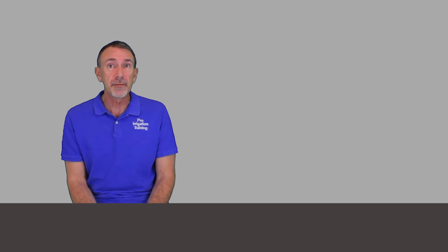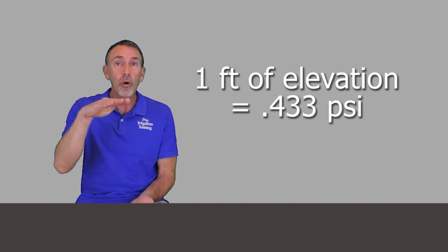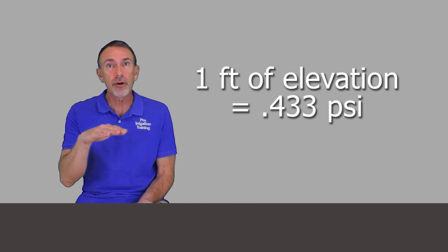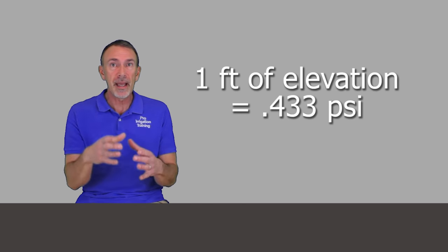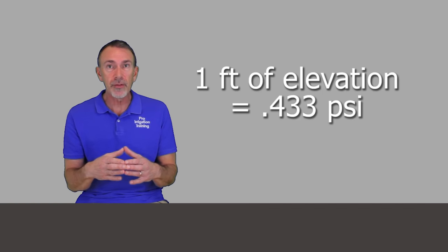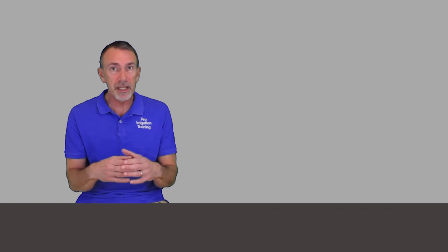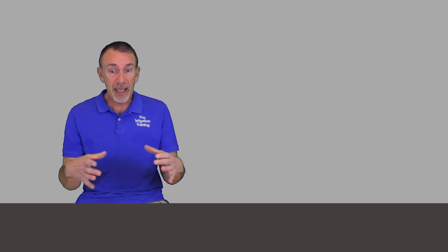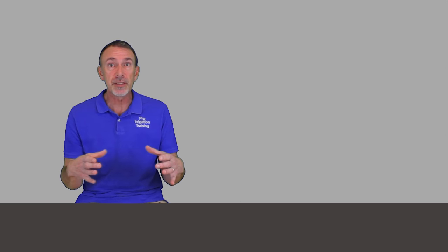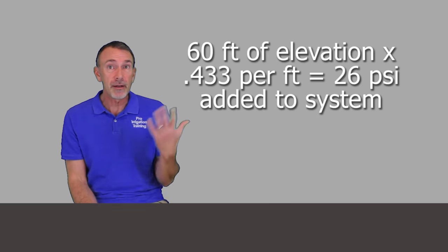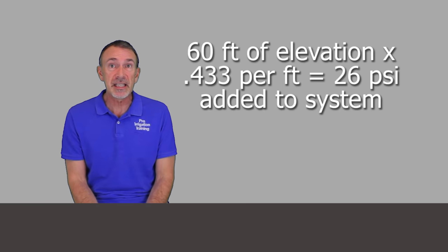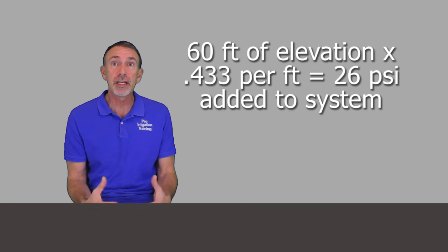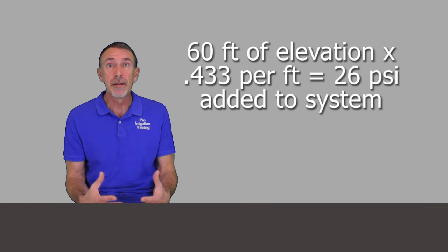What you're going to get from elevation is that for every foot of elevation or for the weight of water for one foot of water in a pipe is 0.433 pounds per square inch. Now it doesn't matter the size of the pipe whether it's a one inch pipe or a 10 inch pipe, it's not cumulative for each square inch inside the base, you're gaining 0.433 per square inch. When you're looking at a water tank that may be 60 feet up so they're getting quite a bit of additional pressure that's pushing into the lines and pushing water through.